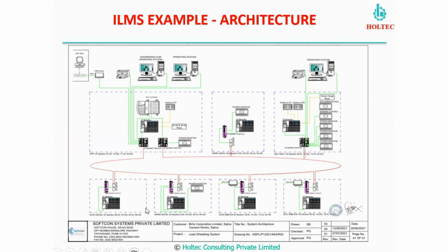All the information required will be gathered by this controller through a distributed IO system, which is distributed at various locations in the plant, and will come to this controller. In addition to that, we get parameters from the generator, from the various power monitors, and from other relays also. Varieties of relays will be there that we have introduced, because we need to operate the trippings also, fast trippings also.